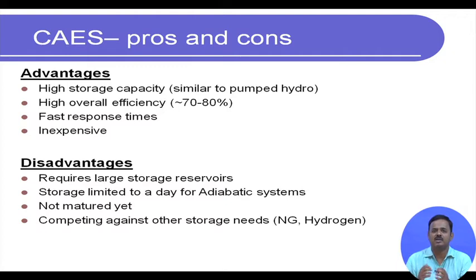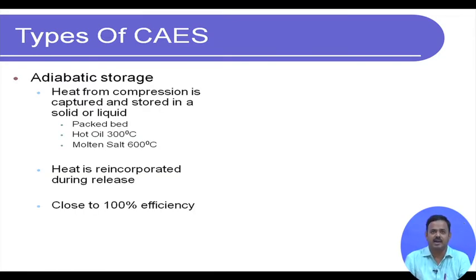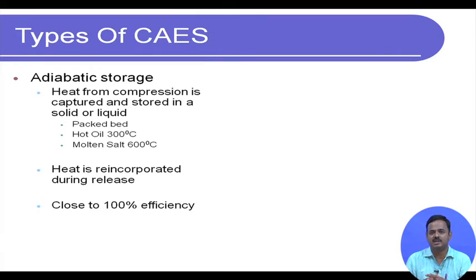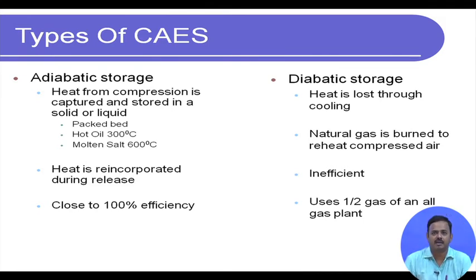There are different types of CAES. Adiabatic storage: heat from compression is captured and stored in a solid or liquid medium — packed beds, hot oil, and molten salt are examples — and re-incorporated into the compressed air during release. Efficiency is close to 100% if the off-peak storage and peak release happen within a day; otherwise the regenerative heat exchanger and reservoir will lose the captured heat.